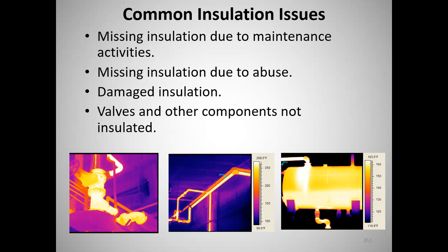They had a major money-making operation going. They were very fortunate. Anyway, they had this small little boiler, and they were making some steam. I went in there and looked at it with the infrared camera. They did not have one stitch of insulation on their whole steam system. Not one.